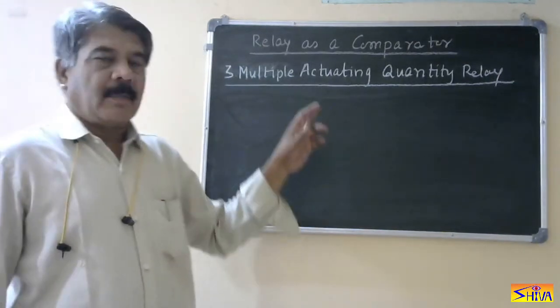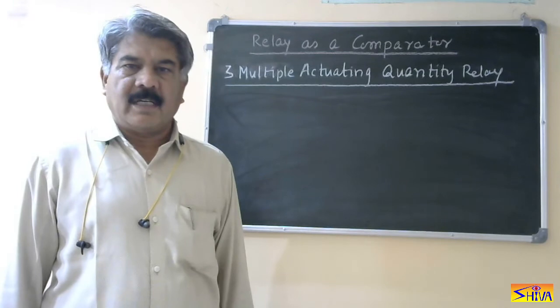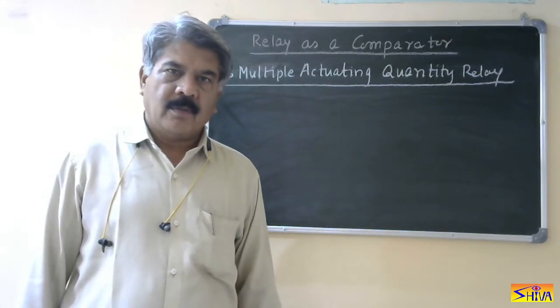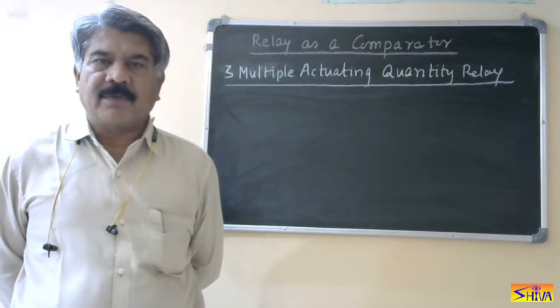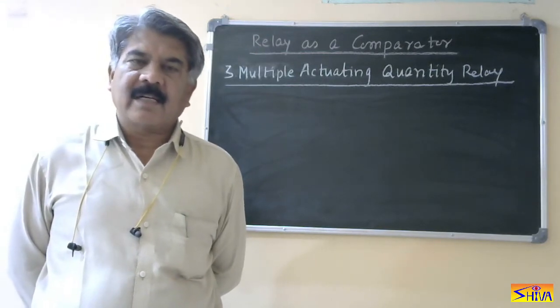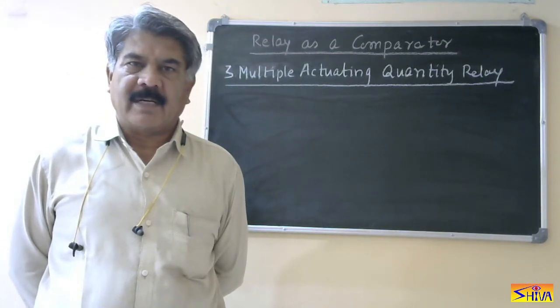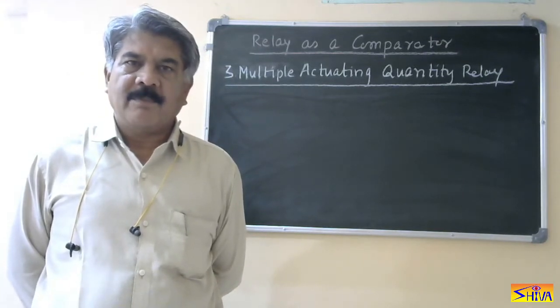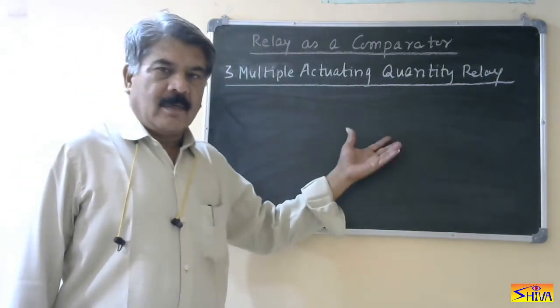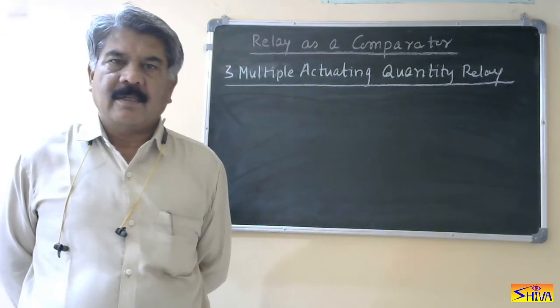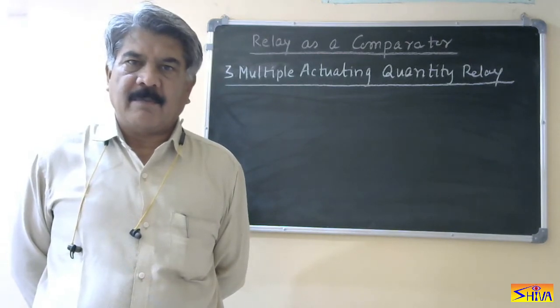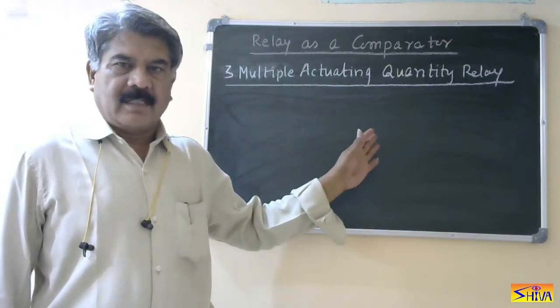Next is the multiple actuating quantity relay, or multiple actuating quantity comparator. As the name indicates, the number of actuating quantities is more than two. In power systems, sometimes we need non-conventional characteristics like quadrilateral, trapezoidal, elliptical, and so on. These characteristics cannot be generated by a double actuating quantity comparator. So we need more than two quantities — these non-conventional characteristics can be generated by more than two actuating quantities relays.